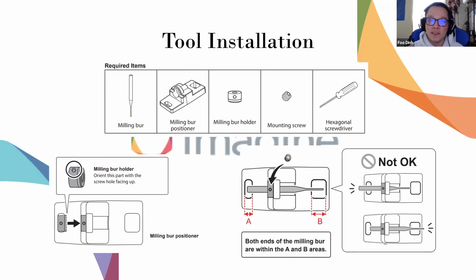Yep. New users especially. They hire new people and don't walk them through it as much, or the people don't pay attention as much, and it happens. It's a small thing that can make a big difference, right? But it seems like on the milling burr holder, they make it pretty clear which side is the right side to be facing the cutting end of the tool, right? Definitely does. The problem that I've seen is they don't use the milling burr positioner, the holder. There we go. Use the tools that are included. That's the moral of that story. Yeah, they try to eyeball it, which causes problems like that, as well as other issues that you run into when it's measuring the tool.